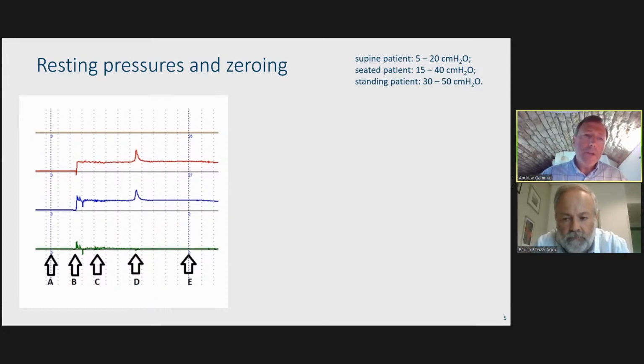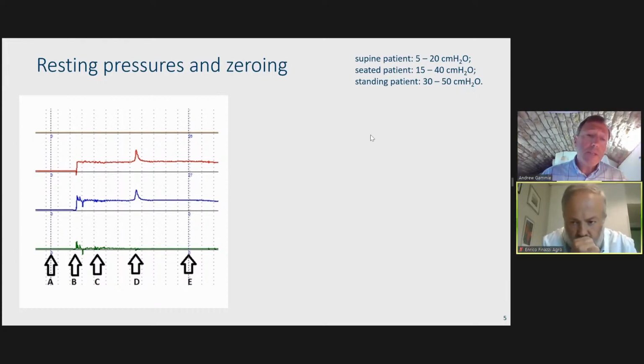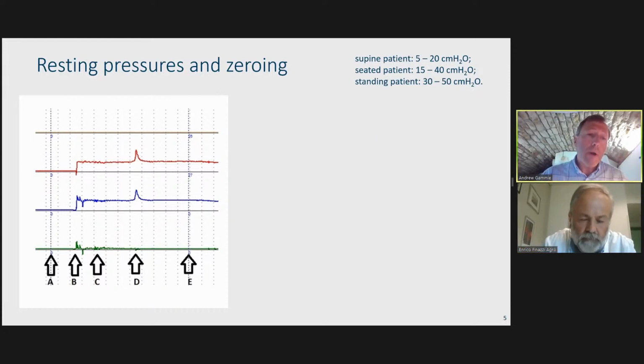And you can see up at the top right here, we've got the standard reference points that have been put in the ICS standards, basically from experience. We know that when you've got good quality measurements, that's the value that you should see in those different positions. So on this trace here, this is an example of what the beginning of a test should look like.